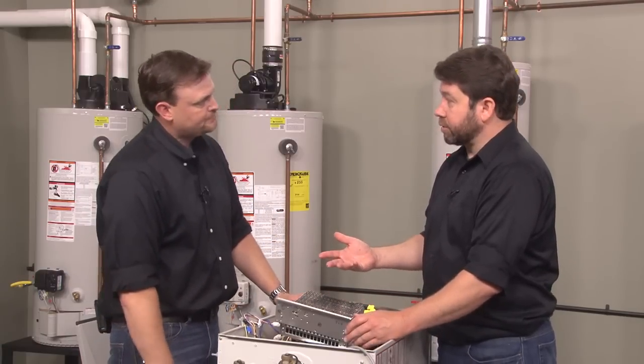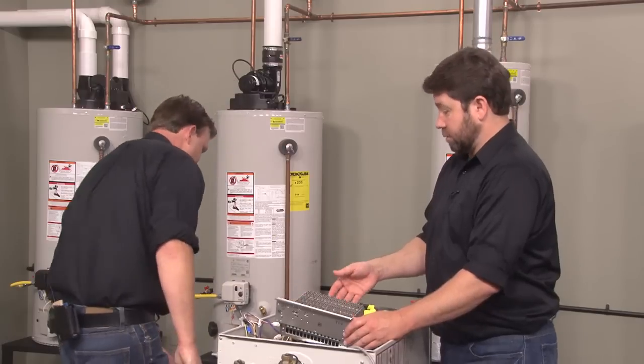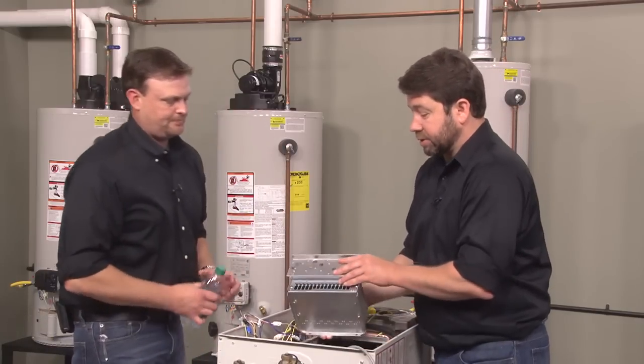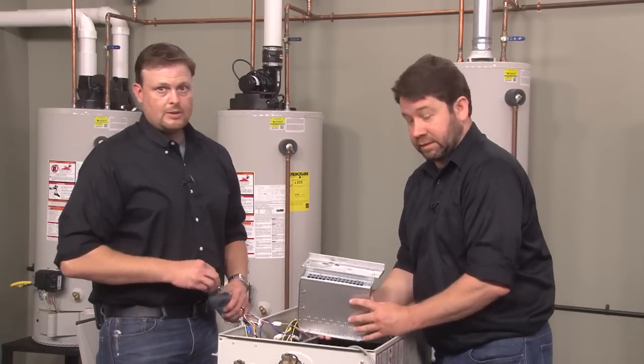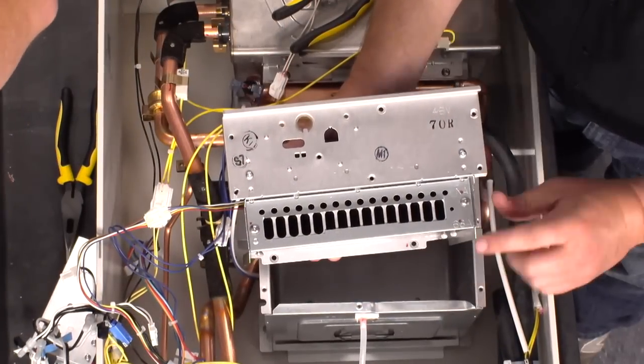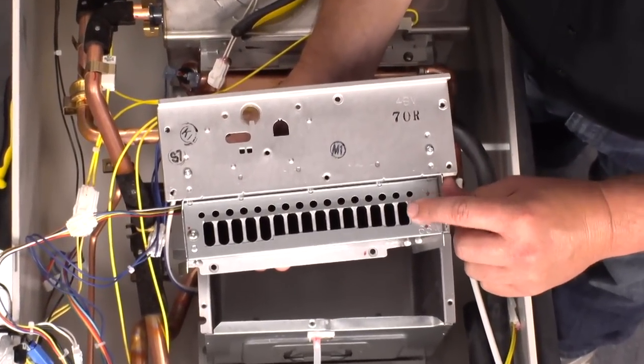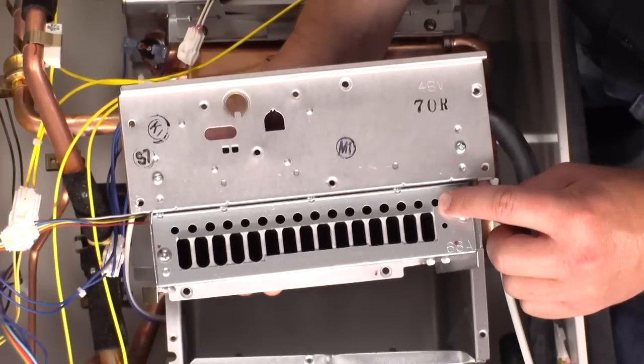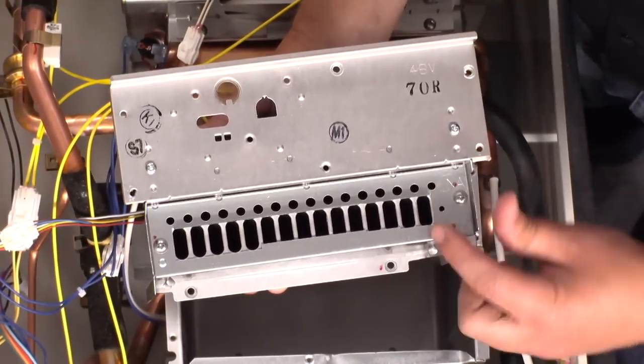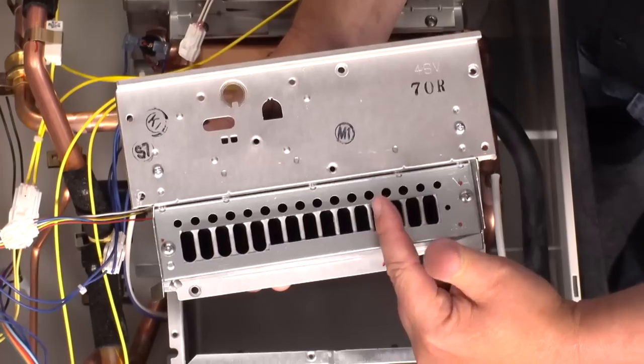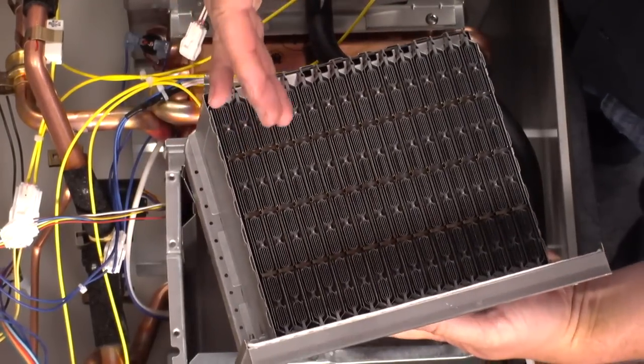And you remember earlier we talked about the AFR? Yes. And the flame rod. If we could get a shot here of the front of the burner again, we see that we've got our larger orifice for our high fire and our smaller orifice for our low fire burners. Right. And they're staggered. Mm-hmm. So we'll have a high flame, low flame, high flame, low flame. Right.